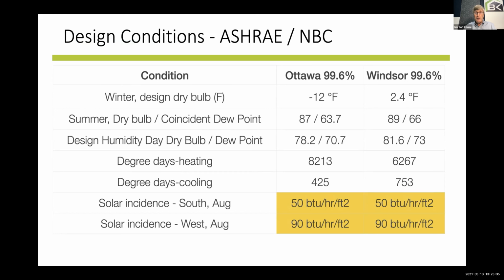But if we looked at Ottawa or Windsor, we're talking about the 99.6% day. That is 99.6% of the time over the last 30 years, according to ASHRAE and the NBC, it's been warmer than minus 12 degrees Fahrenheit. Now, of course, if you're in Ottawa, you say, well, we had a colder day than that.